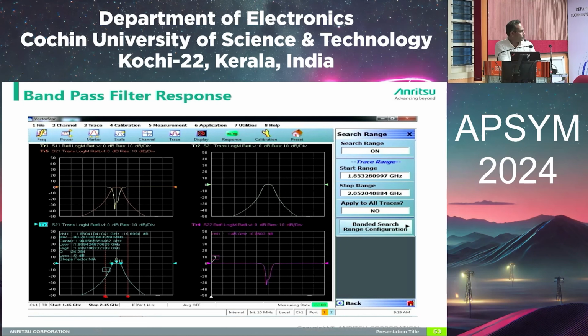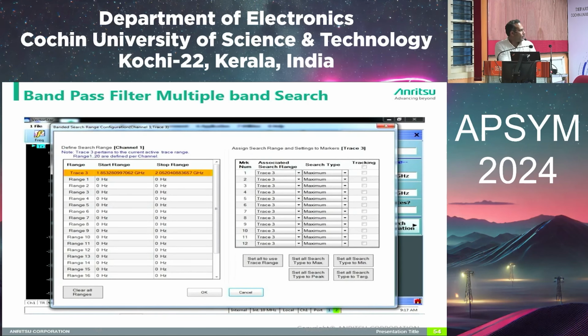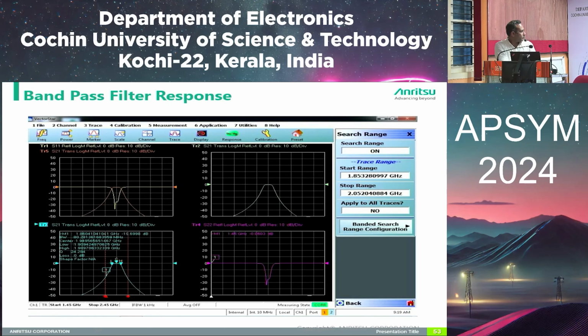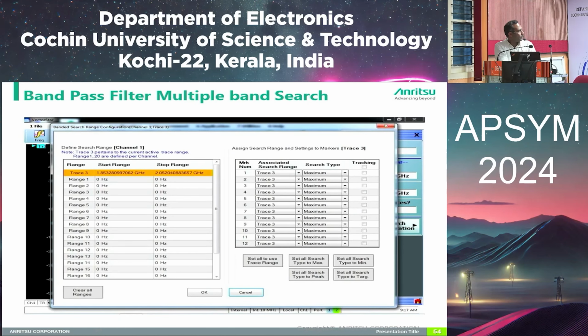There is one more option where we can set the frequency setup also. Suppose we have done the calibration from 1.4 to 2.4 gigahertz. I can make a segmented frequency sweep also, and I can find the value of the return loss on those particular frequency segments. So I can go part by part and analyze the signal for every frequency. And I can set a limit for that and check.